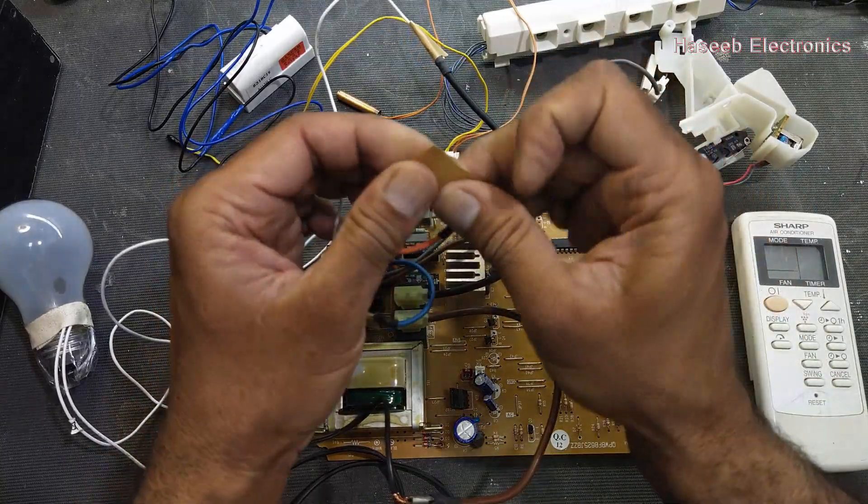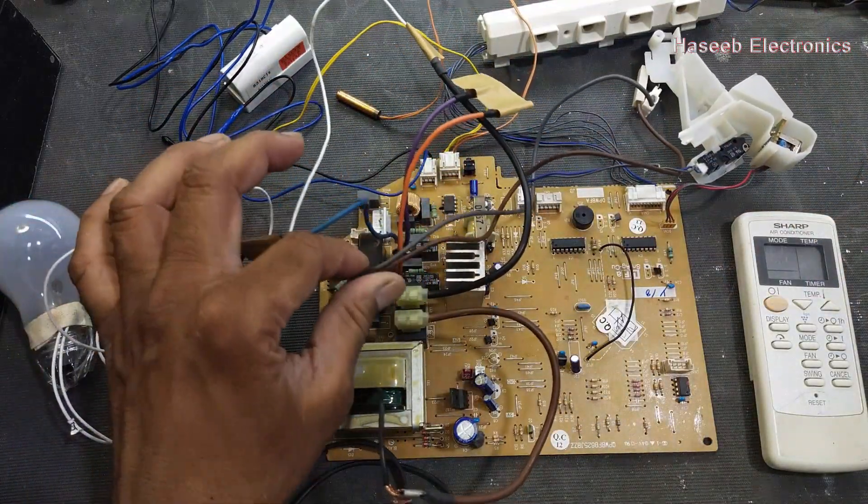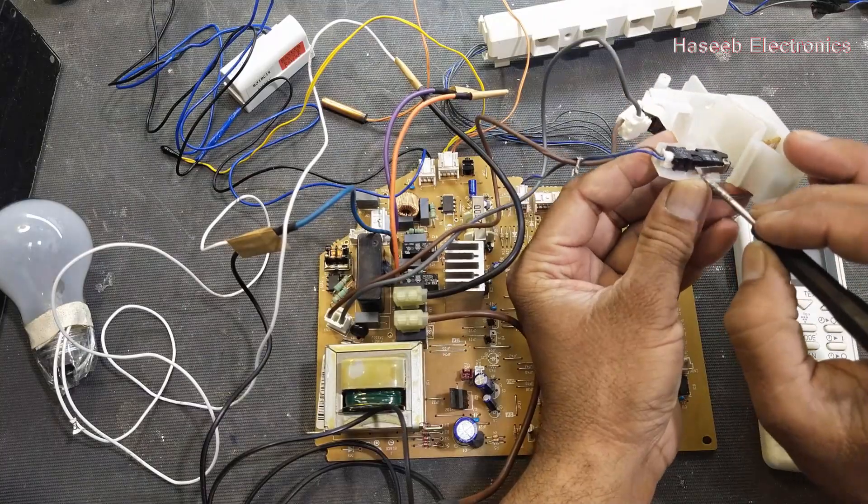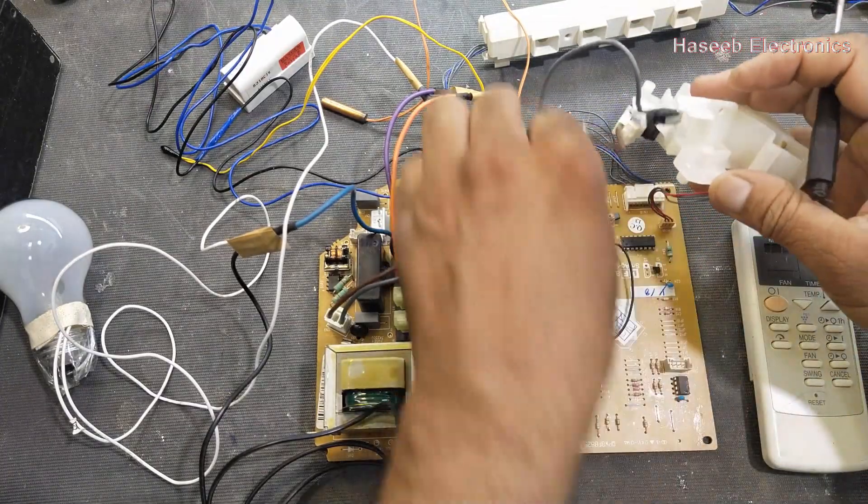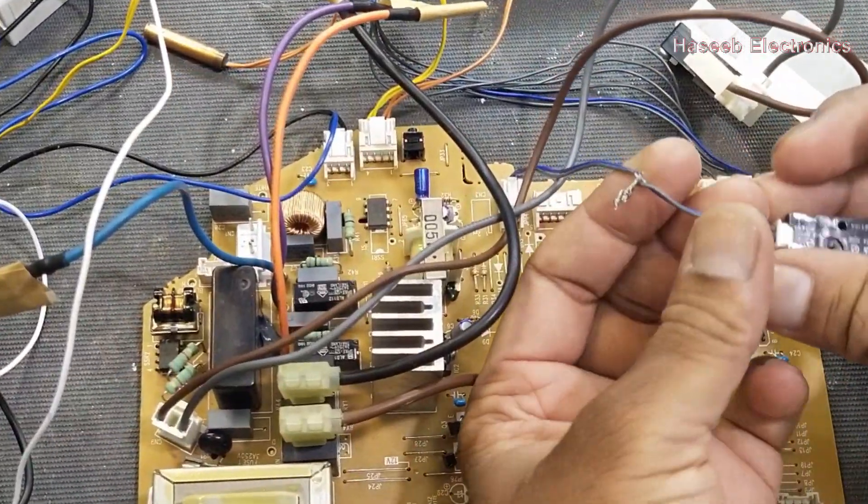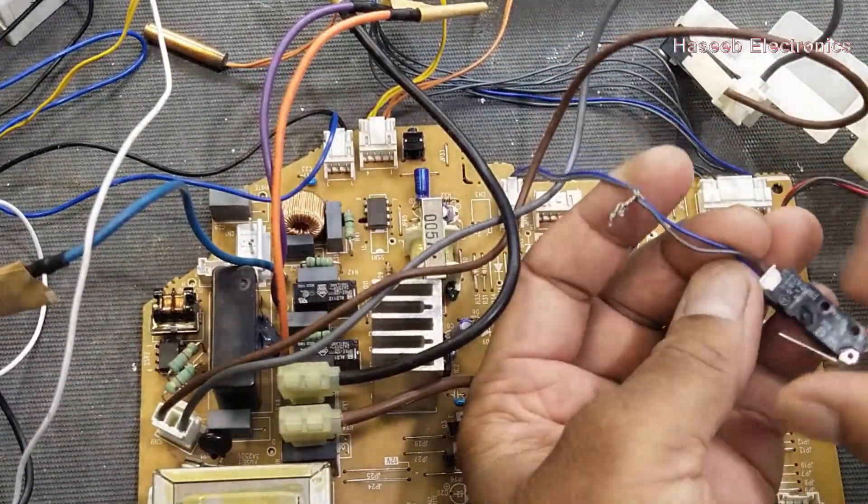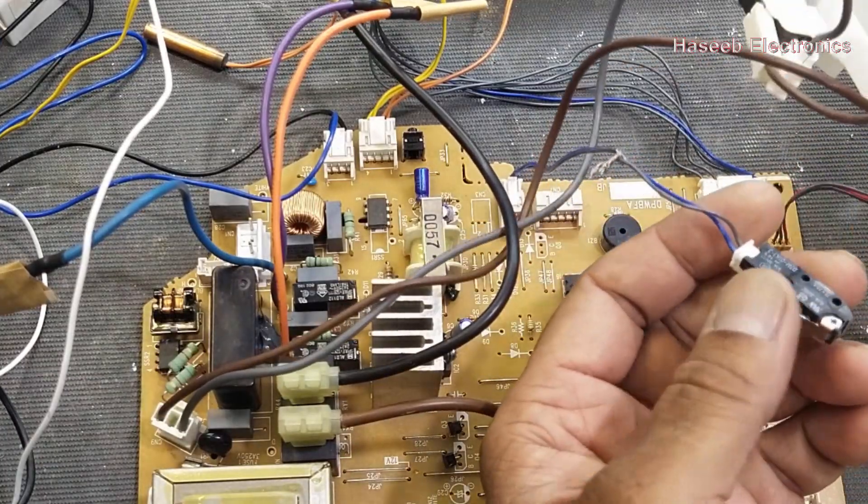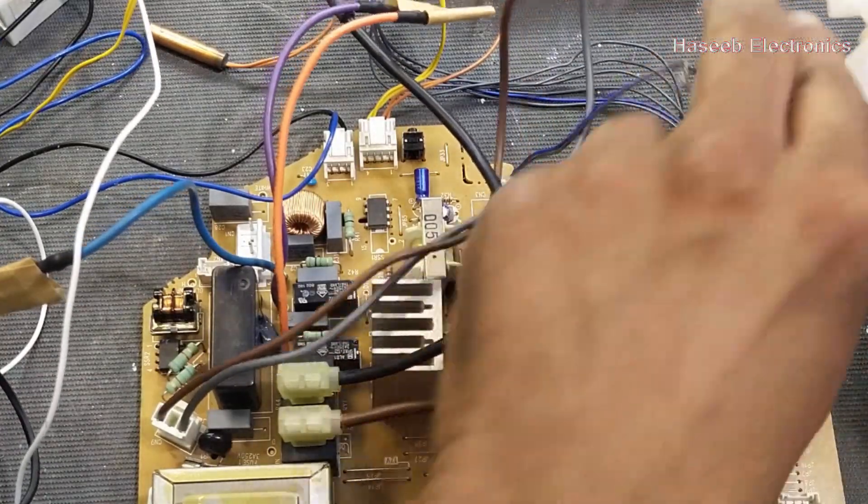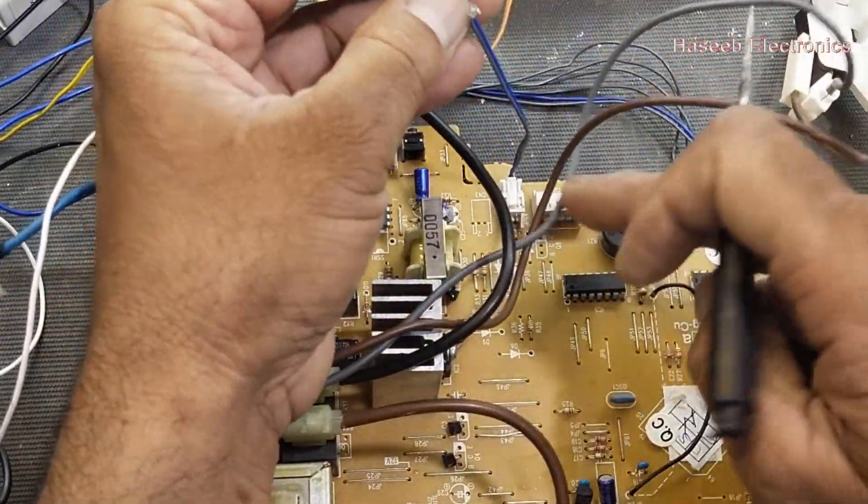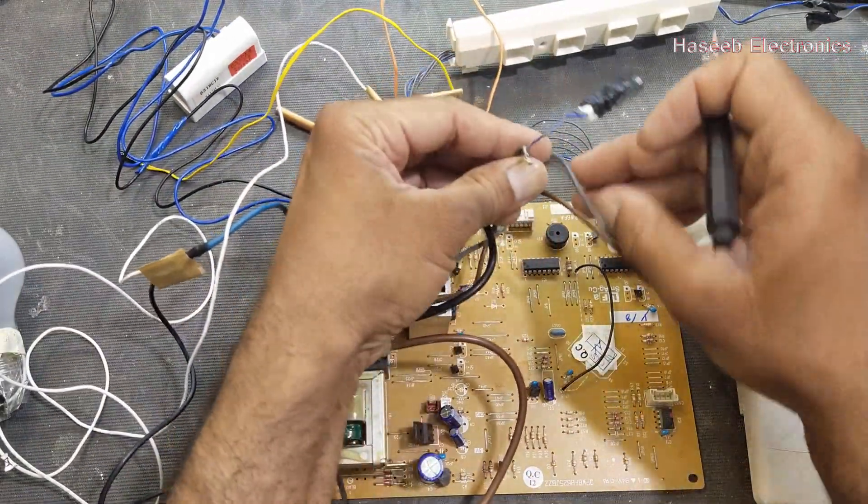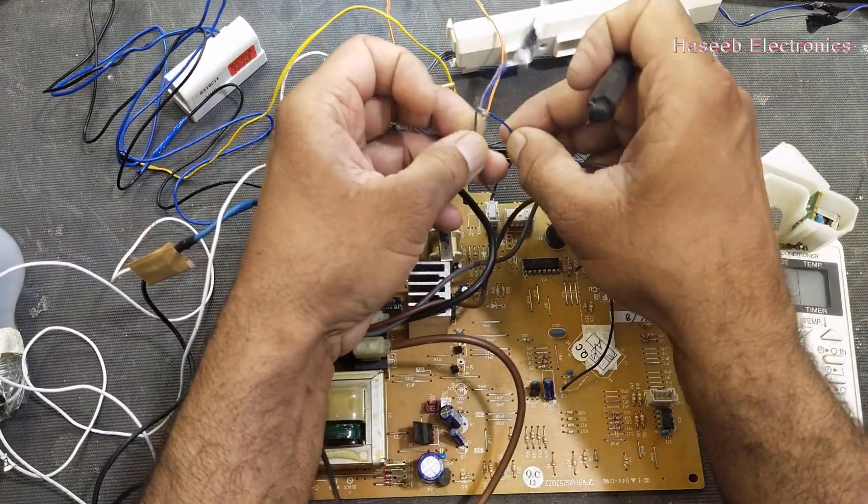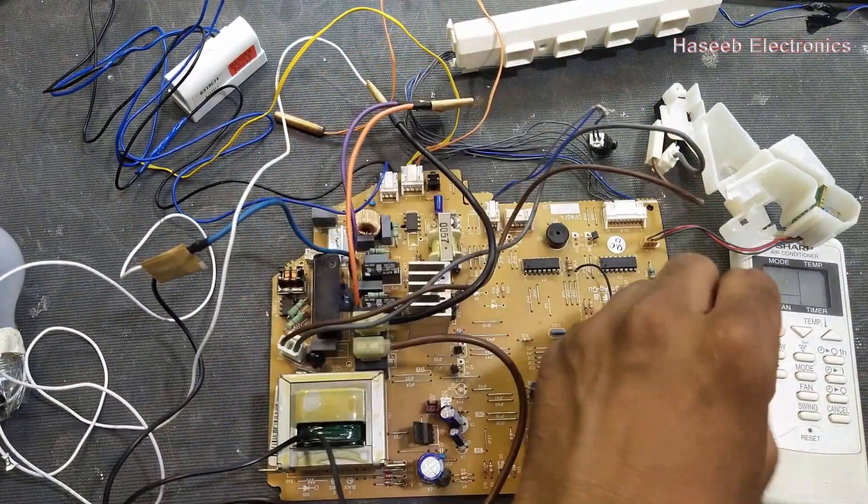It is a quick table test. Now this service mode switch or cleaning mode switch, it is bypassed. Never bypass any safety, because if we enter in service mode for cleaning mode, so this will disable the drive for outdoor unit. But if it is bypassed, the two wires are jumpered together, so it will make problem.